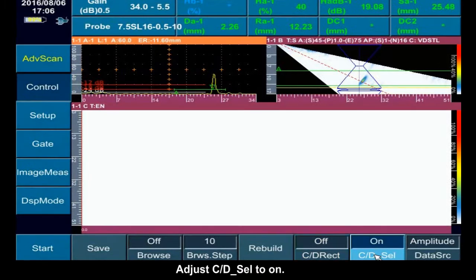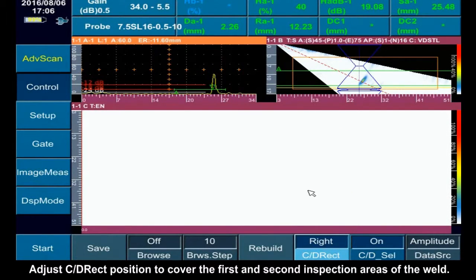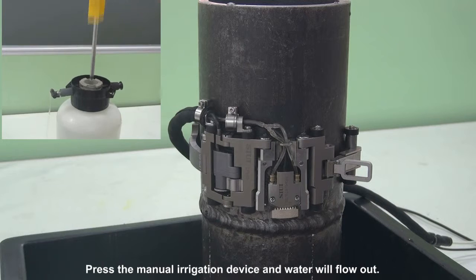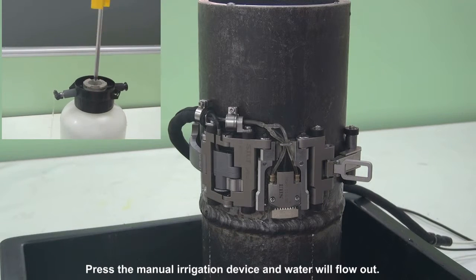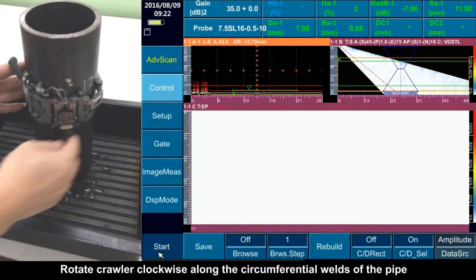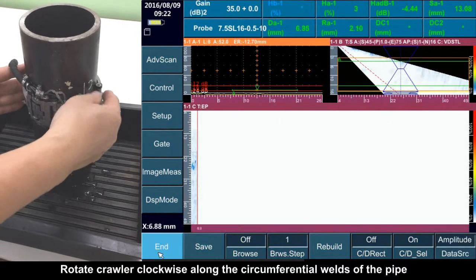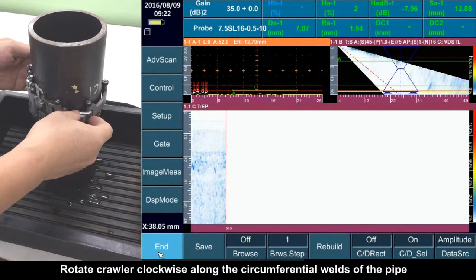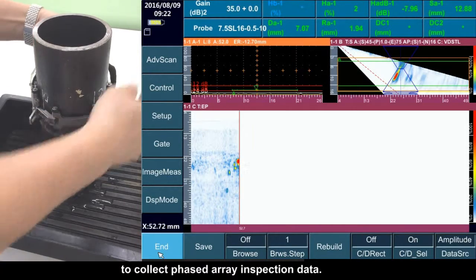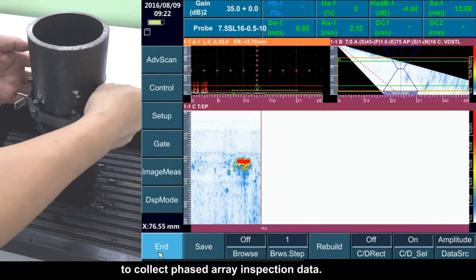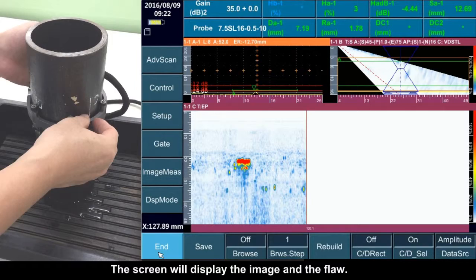Press Control. Adjust CD selection to On. Adjust the CD rectangle position to cover the first and second inspection area of the weld. Press the manual irrigation device and water will flow out. Rotate the crawler clockwise along the circumferential welds of the pipe to collect phased array inspection data. The screen will display the image and the flaw.